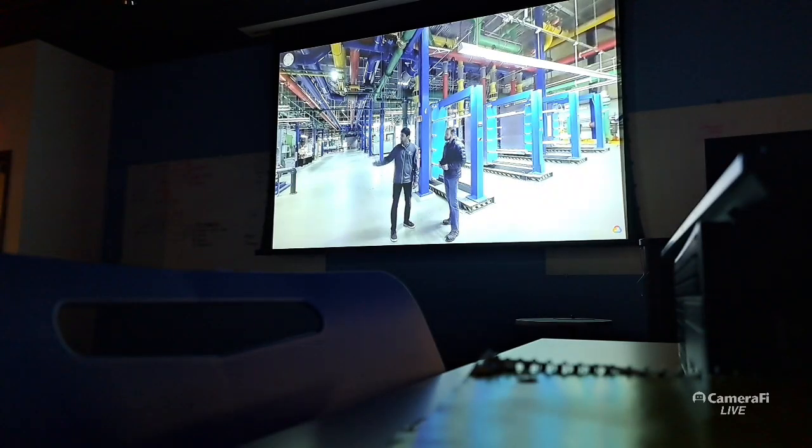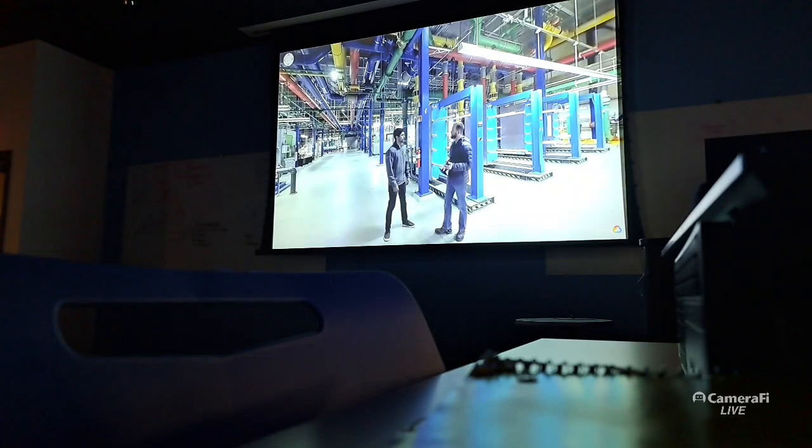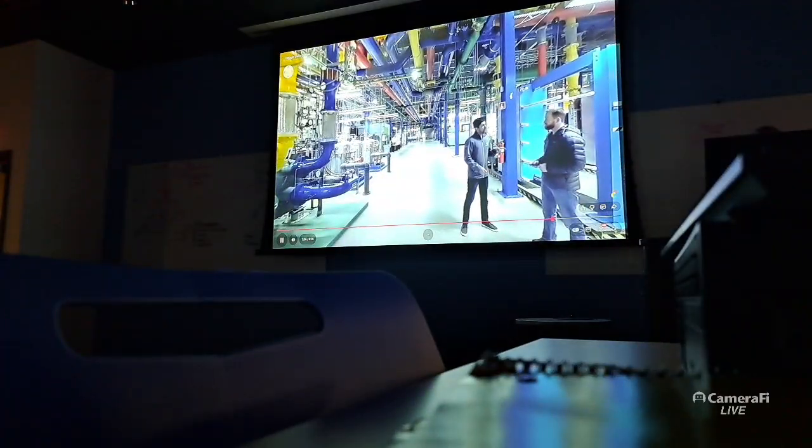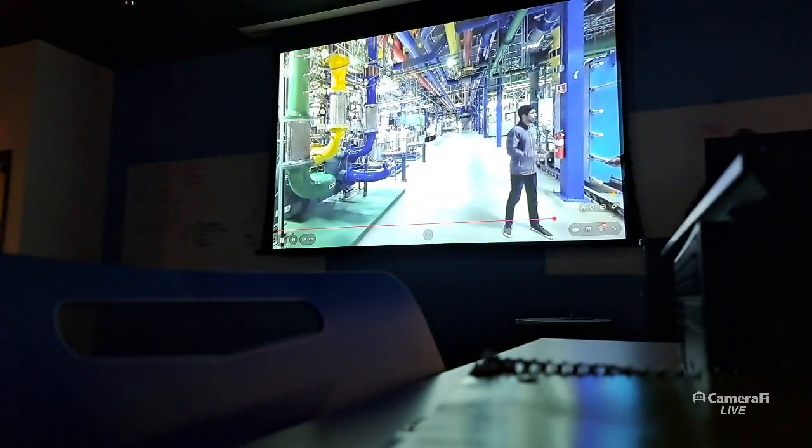Also, what's this big green machine for? Well, this is a chiller. We very rarely use them, but it helps keep the process water temperature in the desired range when it gets really hot outside. Basically helping the cooling tower do its job. In some of our newer data centers, they have no chillers at all. I love how our new data centers are even more efficient. By the way, can we go up and take a look at a cooling tower?